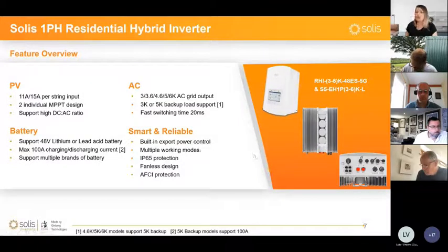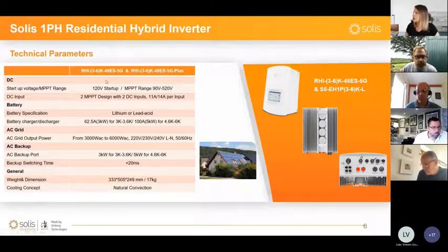Let's see if I have this value here. No, unfortunately not, but I'll have it a little bit later for you, and I'll show you how to check in the technical data sheets, so you can identify for each model the maximum recommended PV input that the system will allow, because that is very important when you're designing your system.